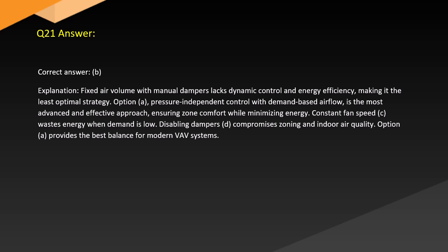Fixed air volume with manual dampers lacks dynamic control and energy efficiency, making it the least optimal strategy. Option A, pressure-independent control with demand-based airflow, is the most advanced and effective approach, ensuring zone comfort while minimizing energy. Constant fan speed, C, wastes energy when demand is low. Disabling dampers, D, compromises zoning and indoor air quality. Option A provides the best balance for modern VAV systems.